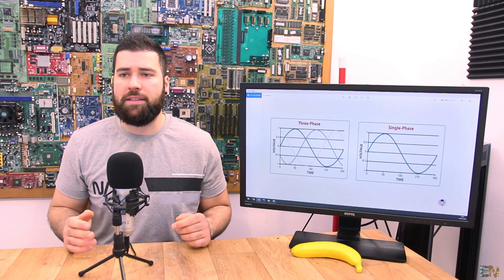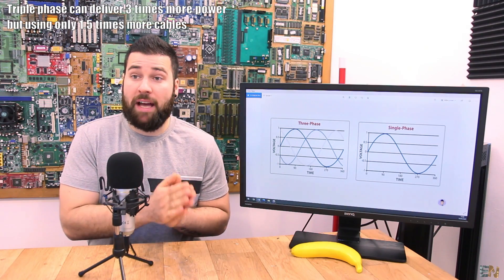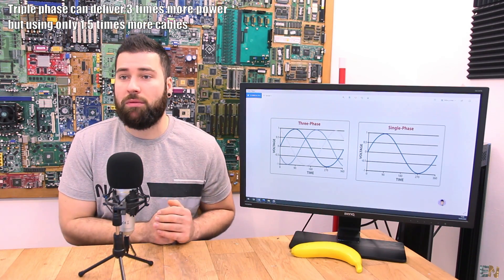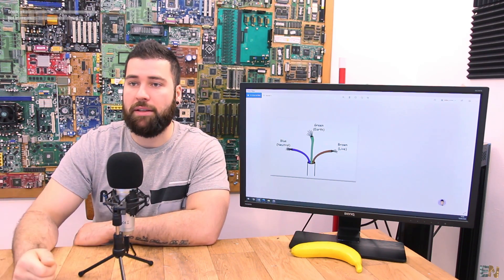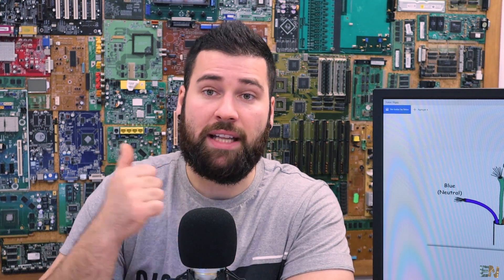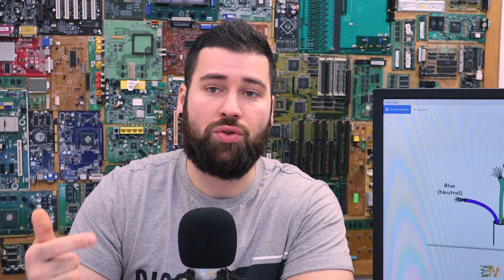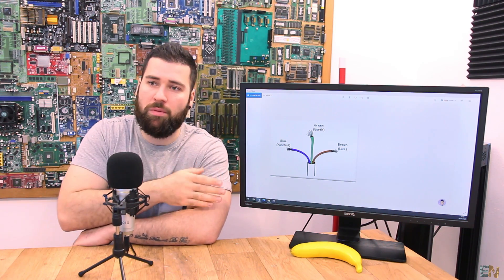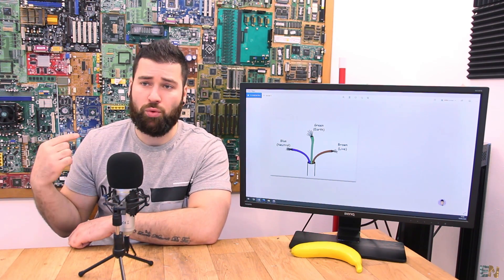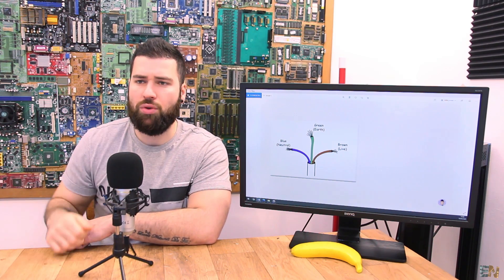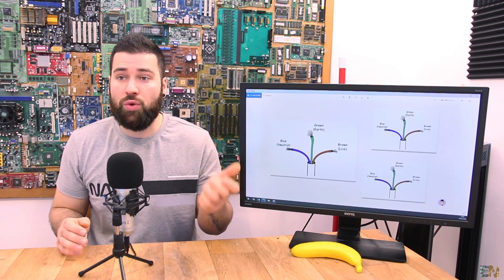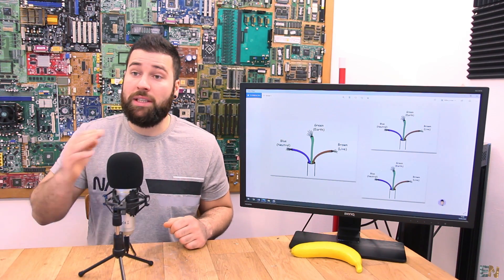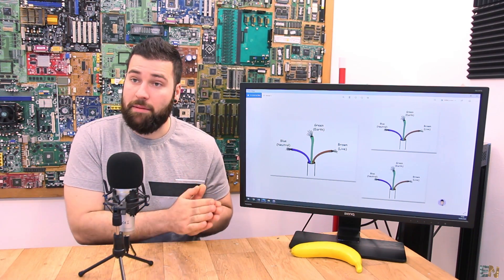This high power transmission has 3 phases — and why is that? Compared with a single-phase transmission, we have the same phase-to-ground voltage but 3 phases, so we can deliver 3 times the power using only 1.5 times more wires. In single phase, we have a live wire and a neutral as return path. If you wanted 3 phases that way, you'd need 6 wires — 3 live and 3 neutral. But in a triple-phase system, this is not necessary.